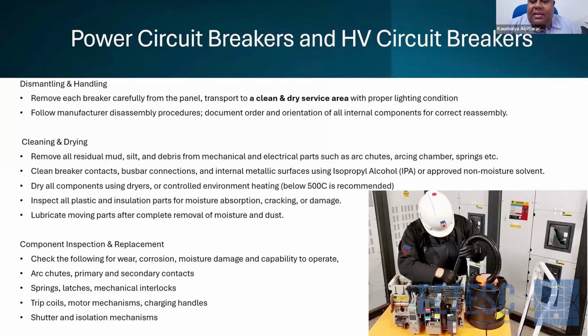Power circuit breakers and HV circuit breakers, ACBs and high voltage circuit breakers. Yes, they can be reconditioned. First, you have to remove them, dismantle them, and take them to a place where it is dry. The usual cleaning practice applies, but you have to take them completely apart, and cleaning and drying has to be done in a very good manner.